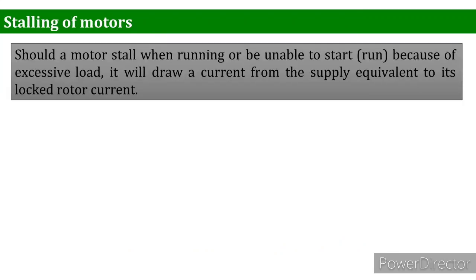We have the stalling of motors. Should a motor stall when running, or be unable to start because of excessive load, it will draw a current from the supply equivalent to its locked rotor current. This is very important. If the rotor is jammed due to some mechanical problem, what will happen? The motor draws an excessive current. When the motor is drawing an excessive current, it ultimately heats up the whole winding. As a consequence, if the protection is not installed, the motor winding heats up, and if proper safety is not attached, the winding will burn out or damage the whole motor.